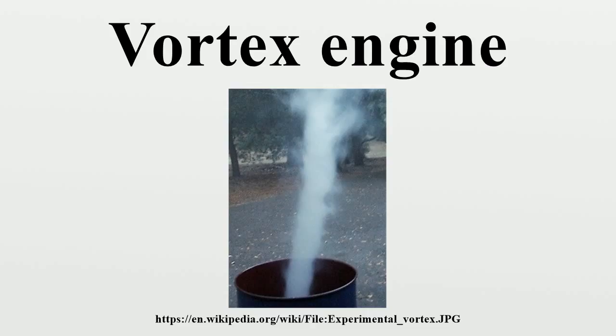Air-driven turbines and constrictions at the inlet of the cooling tower drive electric motor generators. The generators begin to function only in the last stages of start-up, as a strong pressure differential forms between the base of the vortex arena and the outside air, at which time the bypass louvres are closed. The wall and bump retain the base of the vortex in ambient winds by shielding low-velocity air motion in the base of the arena and smoothing turbulent airflow. The height of the wall must be 5 to 30 times the height of the louvres to retain the vortex in normal wind conditions.